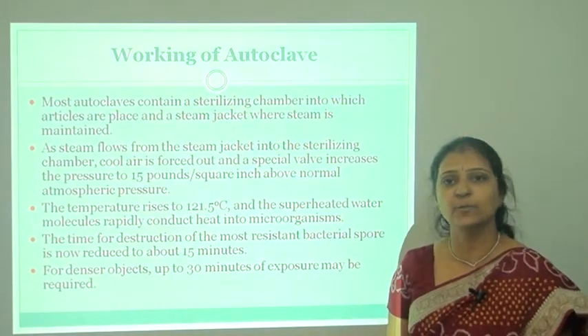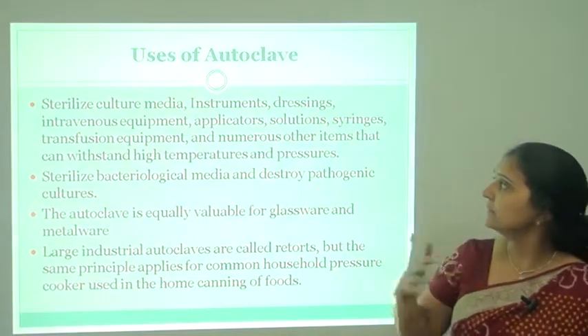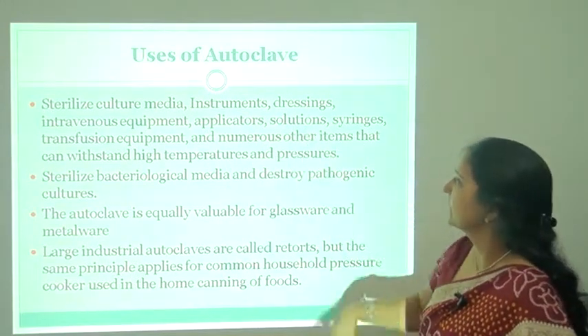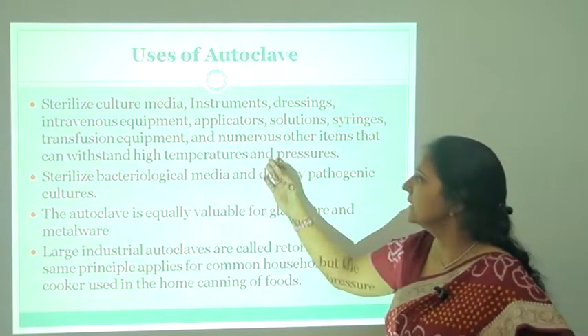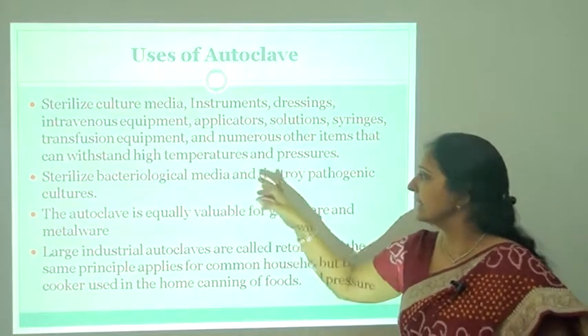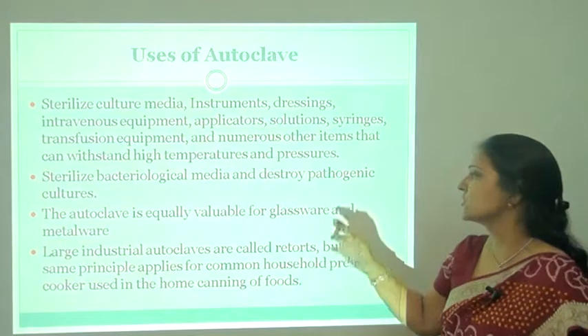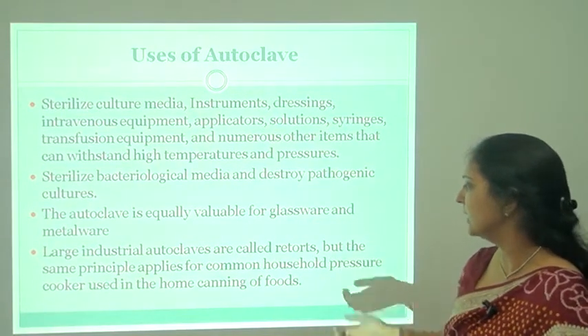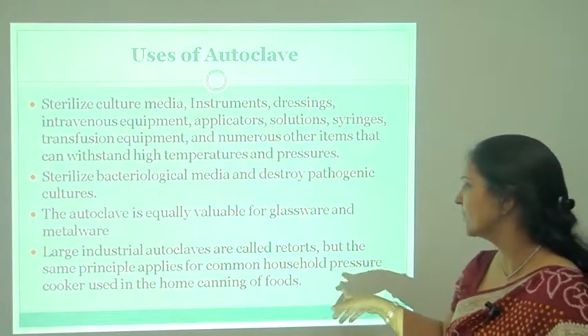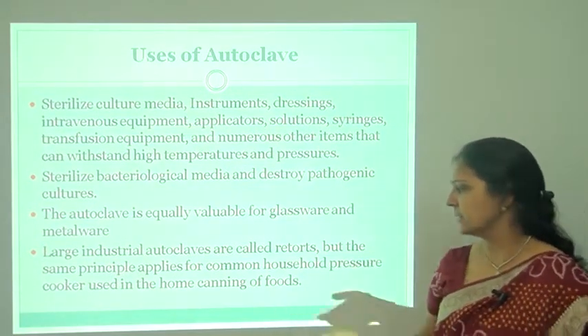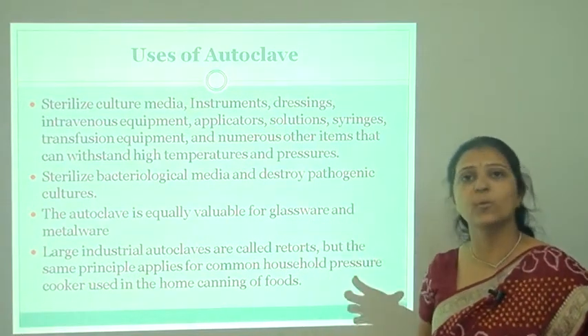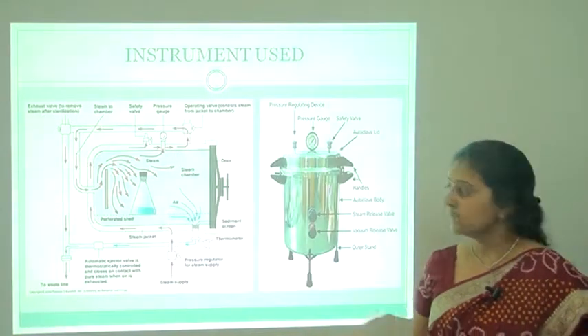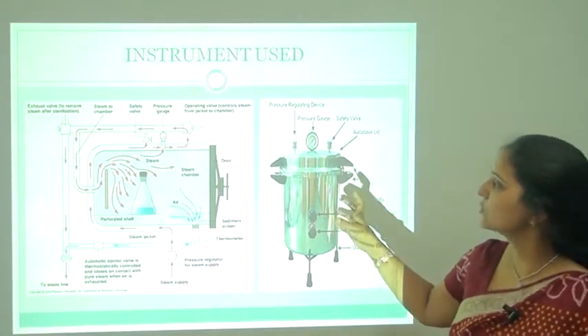We cannot increase the temperature and pressure beyond the standard because higher temperature and pressure may denature the medium components present in the object. The autoclave is used to sterilize culture media, instruments, dressings, equipment, solutions, syringes, needles, and numerous items that can withstand high temperature and pressure. It sterilizes bacteriological media and destroys pathogenic cultures. It is equally valuable for glassware and metalware. Large industrial autoclaves are called retorts, and the same principle applies to the common household pressure cooker.